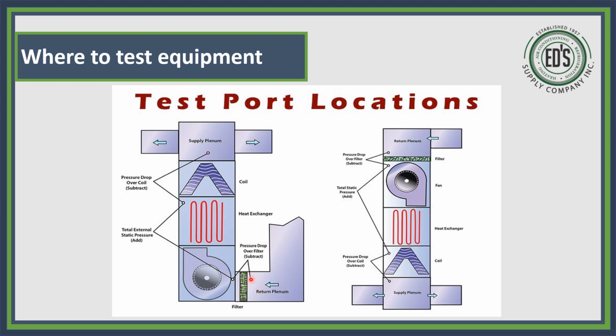Now, this right here, you can do to say, okay, let's say I have a high return on this side, and if I drill a hole and put it here and I see a huge drop, then I know this filter's dirty. It's just as easy to pull it out and look. You know what I'm saying? But if you weren't able to, or didn't have access to it, and you needed to confirm that filter is dirty, you could do that with that pressure drop reading. But to me, that's just another way of doing it. You could really just pull it out and see if it's dirty. But what they're getting at is if it's dirty or if it's too thick for that airflow.